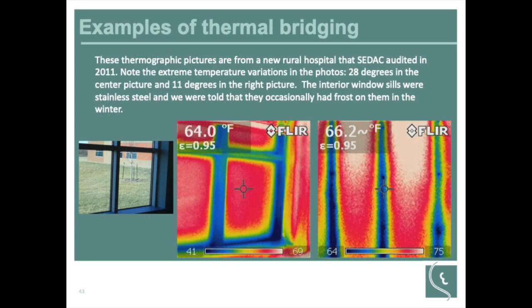Here's an example of thermal bridging. SEDAC had been called out to a healthcare facility down in southern Illinois, and the reason we were there was comfort issues. This was a brand new building, probably wasn't even 2 years old when we came and looked at it. It's like, this is a 2-year-old building, why are we being called in to look at it? And so something that we identified is, looking at this window, here's the normal photograph, and then we have our infrared image here. So you can see, here you got double pane, thermally broken glass, very well done. They forgot and didn't order thermally broken sashes. And so, the window's okay, but all the metal in there is just leaking heat like crazy.